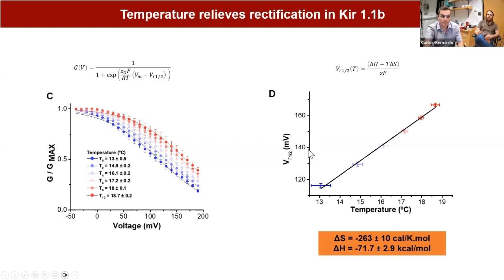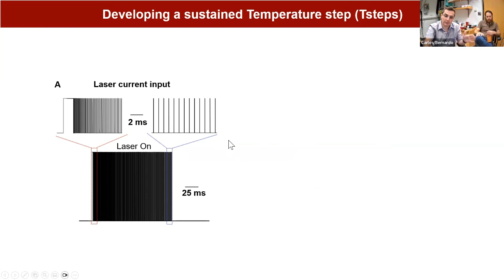So first we apply a laser pulse where more or less we set the temperature that we want. And then after that, we modulate the laser current such that the temperature that we set in the beginning, we're going to be oscillating in that range. And then from that, we have this kind of flat temperature step here. And you can see that in less than 1.5 milliseconds, we can have a change of 9 degrees, and it maintains until the end of the recording. So now we can have a temperature step of about 9 degrees for 150 milliseconds.